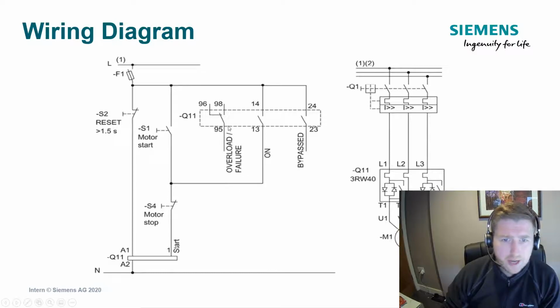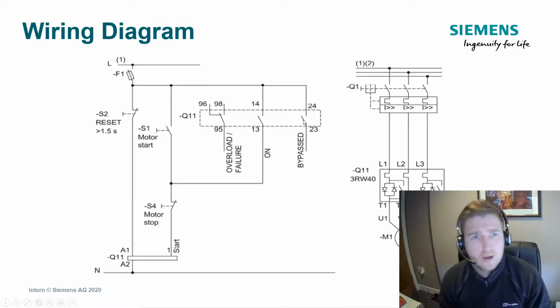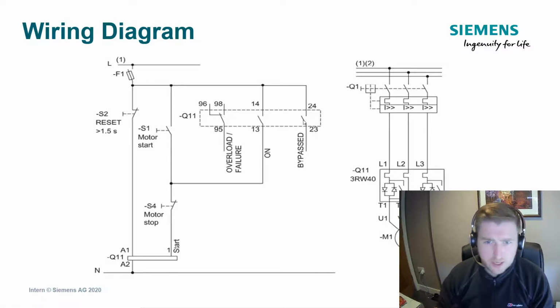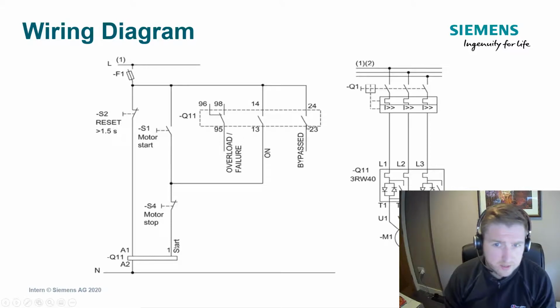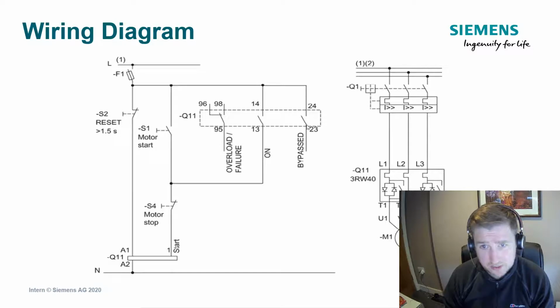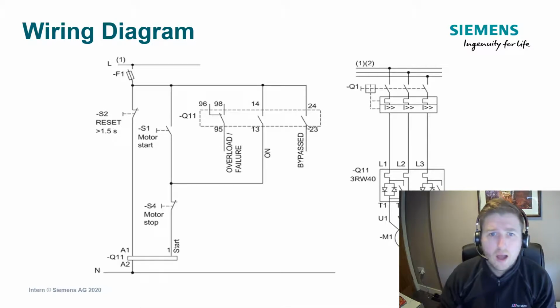You don't actually have to have any of the signaling. That is optional, so you can signal that there's an overload or a potential failure if you wish to with this contact. And then similarly there's also a signal contact here which is called bypass, which we brushed on earlier, which basically gives you a signal to tell you that the device is going through a startup or a stop procedure. So that is the way that you would connect the device.